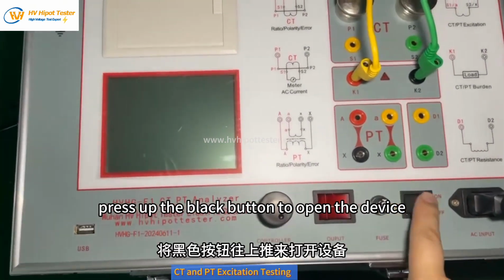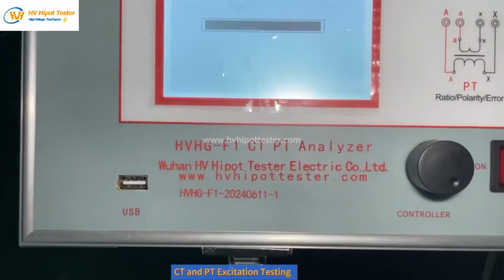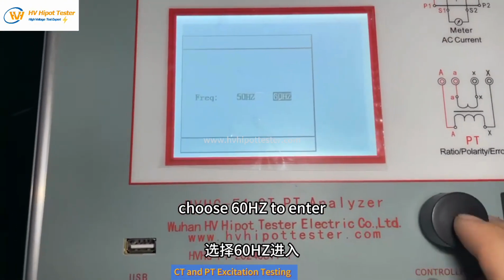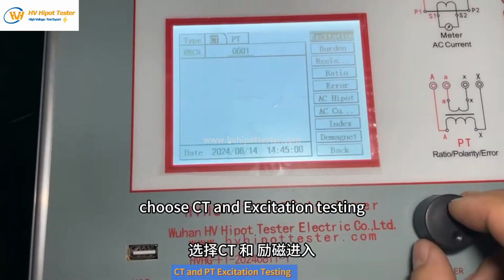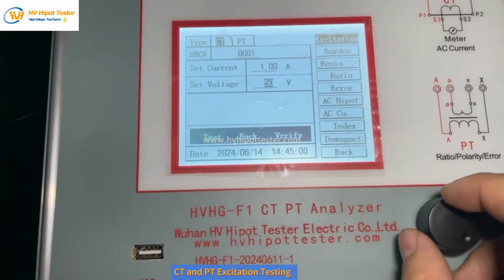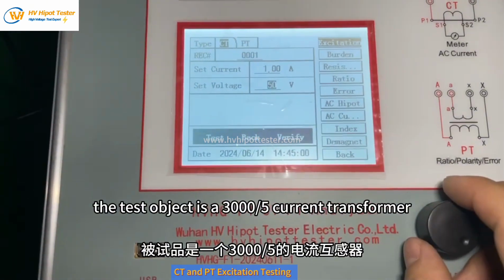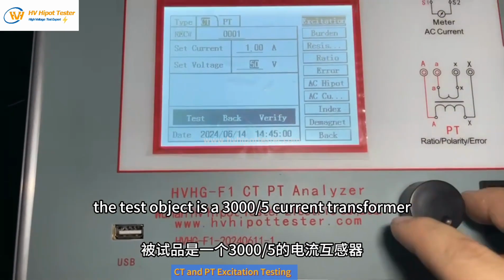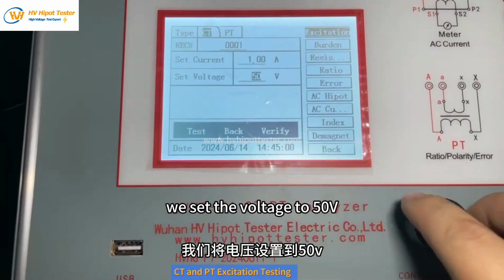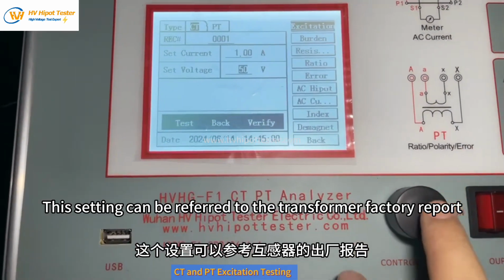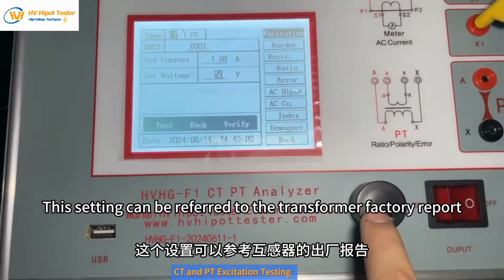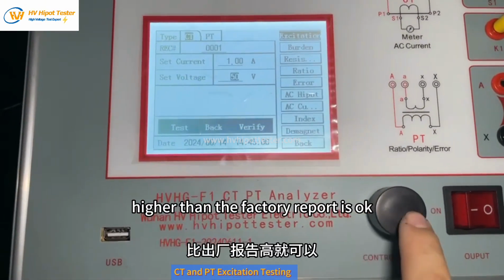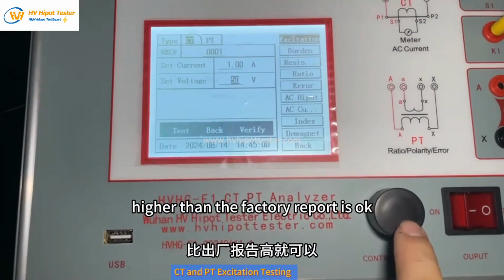Press up the black button to open the device. Choose 60 Hz to enter. Choose CT and excitation testing. The test object is a 300/5 current transformer. We set the voltage to 50 volts. This setting can be referred to the transformer factory report. Higher than the factory report is OK.